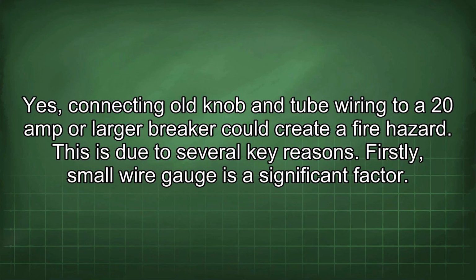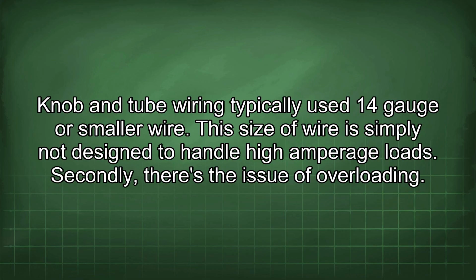Yes, connecting old knob and tube wiring to a 20 amp or larger breaker could create a fire hazard. This is due to several key reasons. Firstly, small wire gauge is a significant factor. Knob and tube wiring typically use 14 gauge or smaller wire. This size of wire is simply not designed to handle high amperage loads.